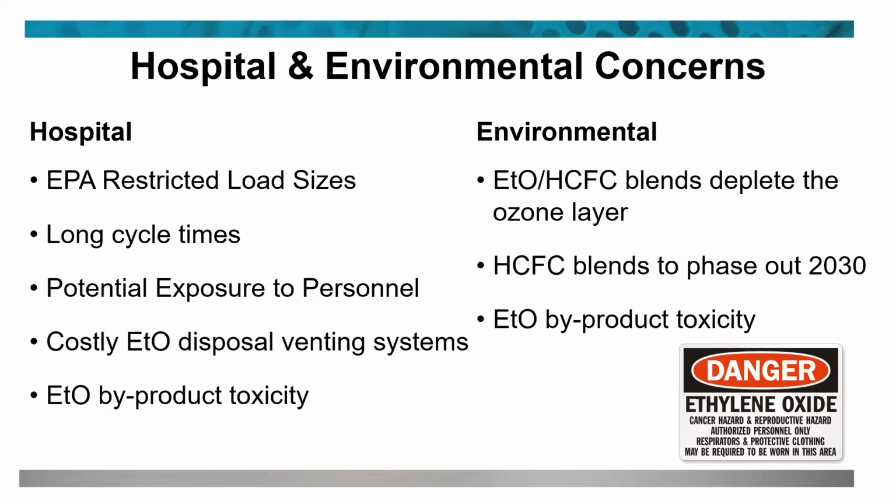So we really want to be careful with this when we use it. From an environmental perspective, the most common problem is the ETO gas blends containing hydrochlorofluorocarbons, which can deplete the ozone in our atmosphere. And so that's why we've gotten rid of more and more of it.